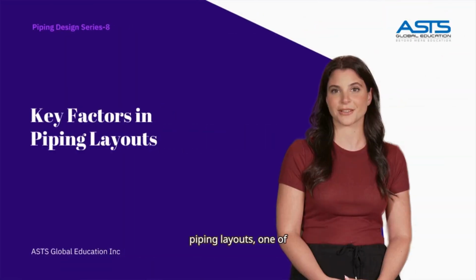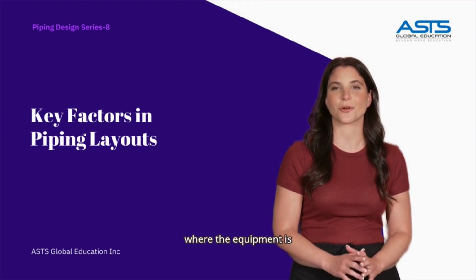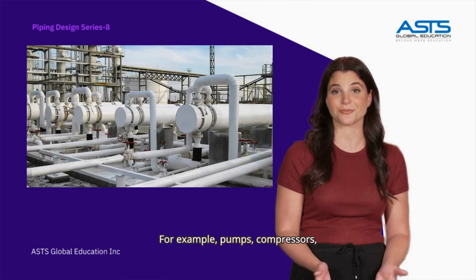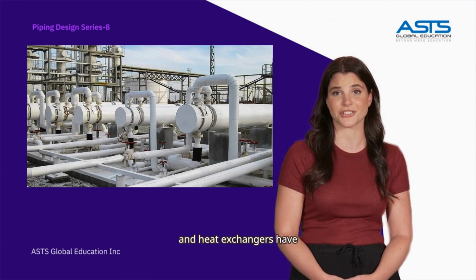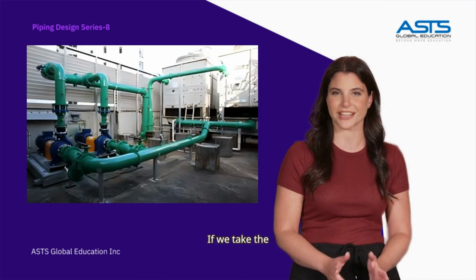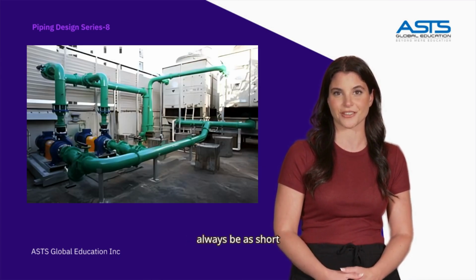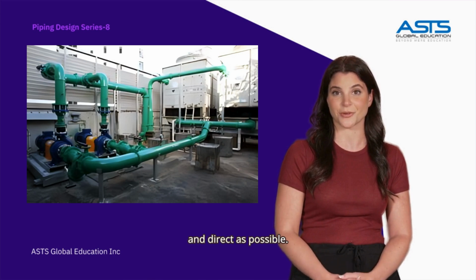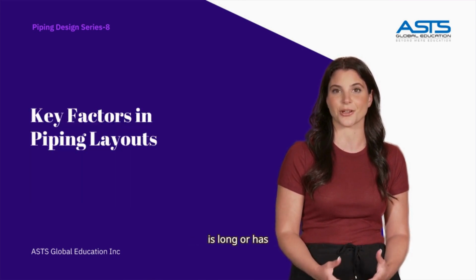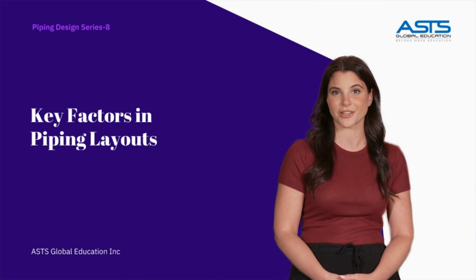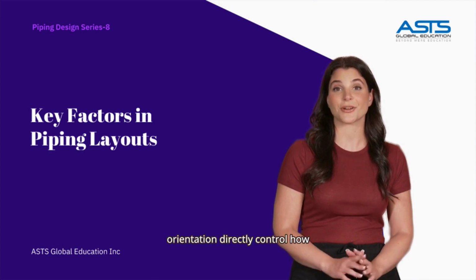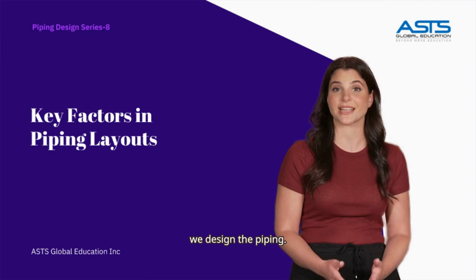When we talk about piping layouts, one of the first things to understand is that the layout always depends on where the equipment is placed. For example, pumps, compressors, and heat exchangers have fixed nozzles, and the piping has to be arranged around them. If we take the case of a pump, the suction line should always be as short and direct as possible. If the suction piping is long or has unnecessary bends, it can cause pressure losses and lead to pump cavitation, which can damage the equipment. So, equipment location and orientation directly control how we design the piping.